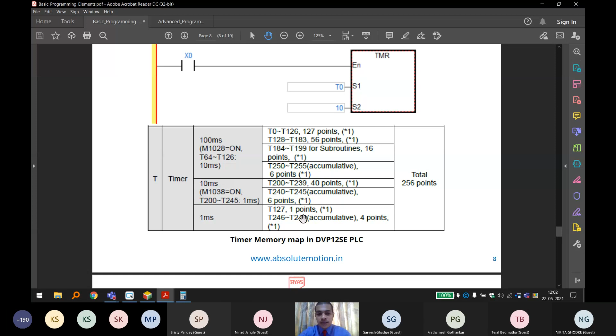If you notice, there are a lot of timers available for the 100 millisecond time base - around 200 timers here. For the 10 millisecond base, there are only 46 timers, and for the 1 millisecond base, there are only about 5 timers. This is because most applications end up using 100 millisecond base timers. The lower the time base you go for, the higher the load on your PLC CPU, which is why they don't give you as many of those timers.